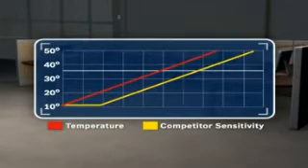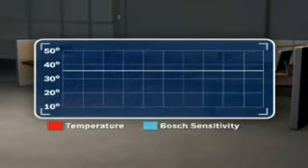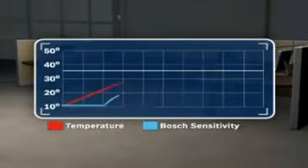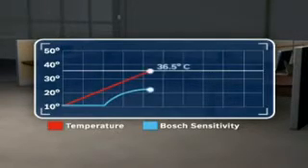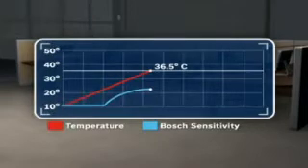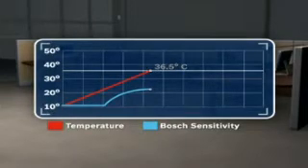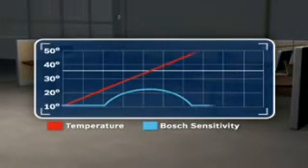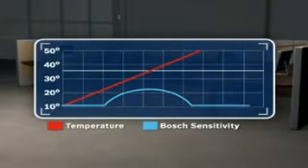At high temperatures, with Bosch Professional Series detectors, the sensor gain increases until the room temperature reaches 36.5 degrees Celsius or 97.7 degrees Fahrenheit - the temperature of human skin. But once the ambient temperature exceeds 36.5 degrees Celsius or 97.7 degrees Fahrenheit, the sensitivity decreases, minimizing false alarms.